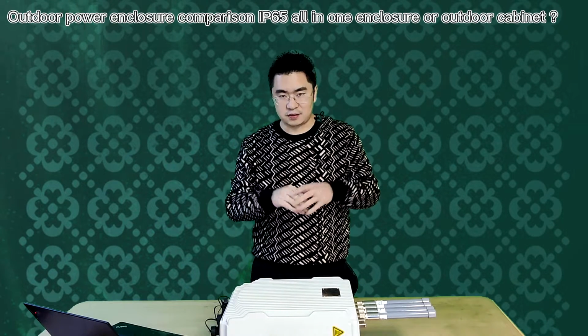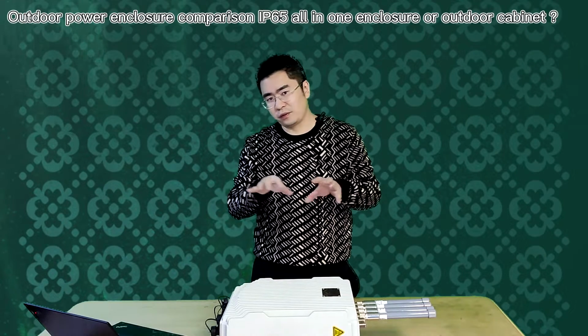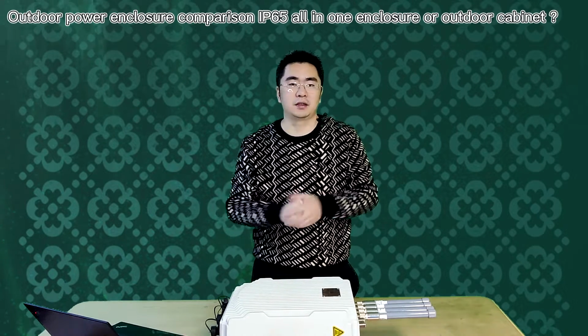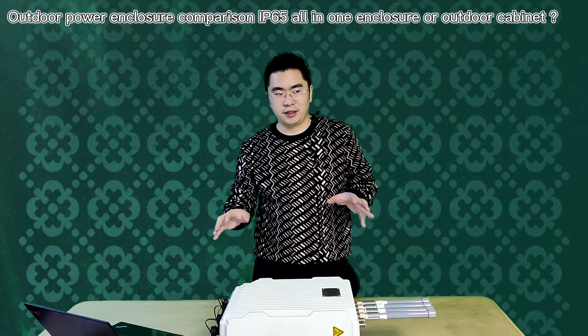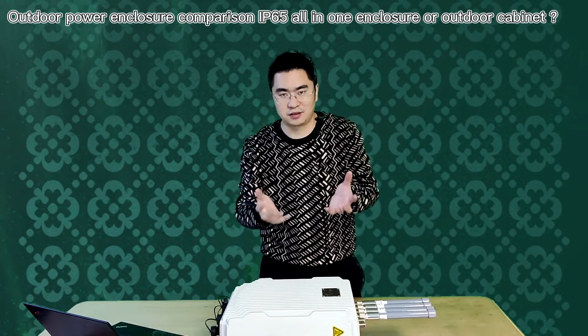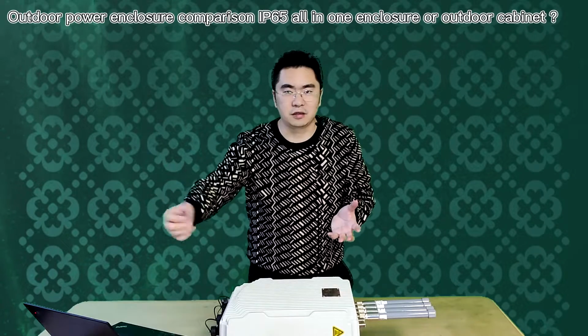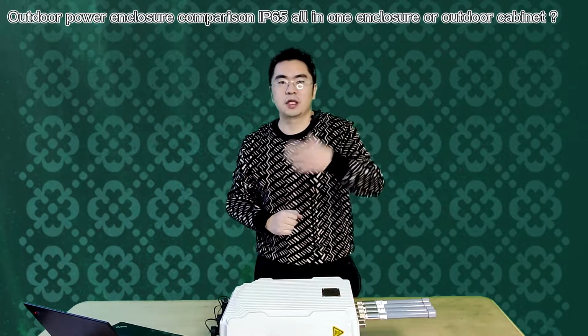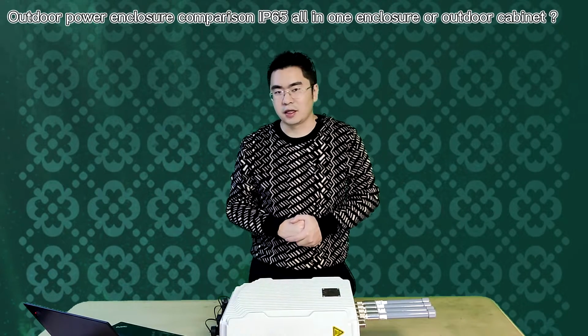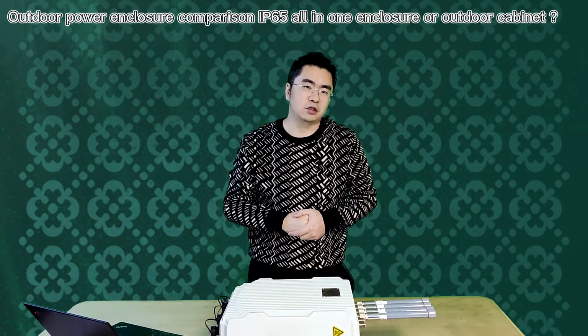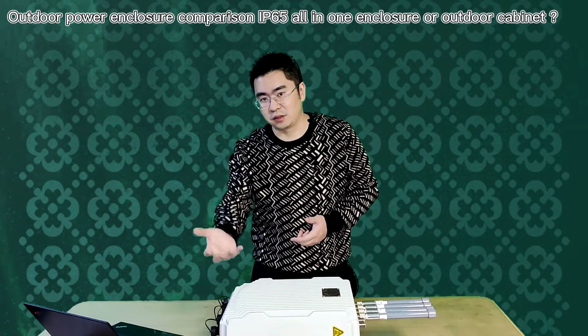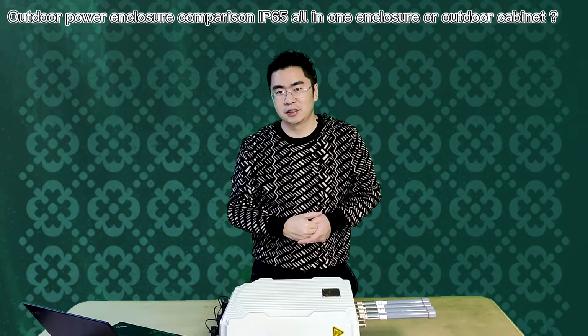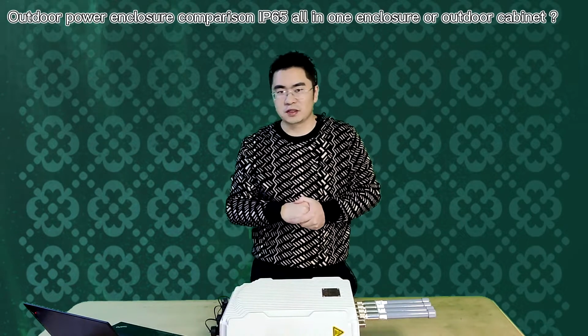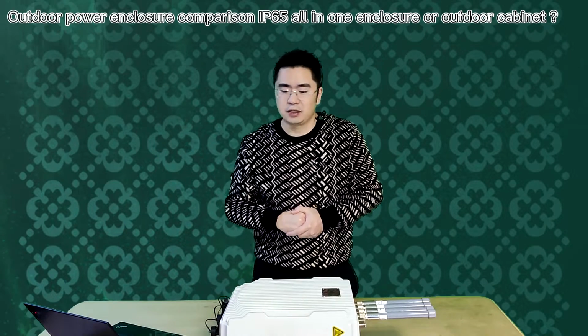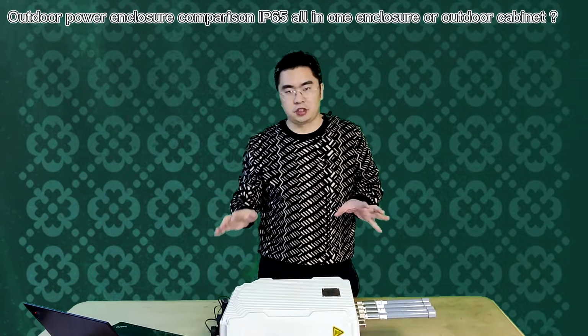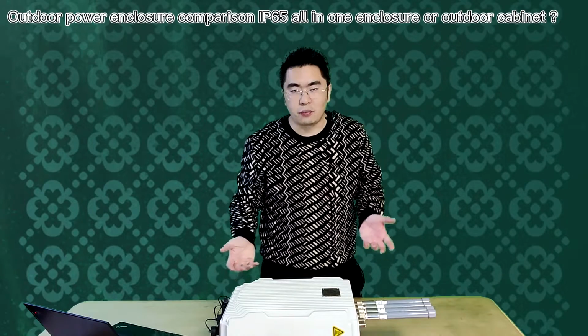If it is a fan system, the problem you will face is that this cabinet is for sure IP55. If it is IP55, it cannot resist the humidity from the air or the salty air from the sea, and if you put it in the jungle, the high humidity will destroy your products. And if you deploy near the desert, sorry, you will face the sandstorm problem. This kind of thing will be a big challenge. In the end, it will increase the operation cost.